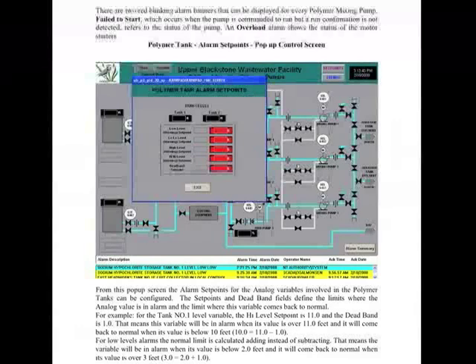Anyway, you guys are all familiar with how deadbands work on level alarms, right? So where it goes into alarm at, say, 10 feet, you have a deadband of 0.5 feet. If you get a high alarm at 10 feet, it will stay in high alarm until the level in the tank gets below 9.5 feet, if your deadband is 0.5. Pretty simple. Are there any other questions, anything that you guys want to know about this system?